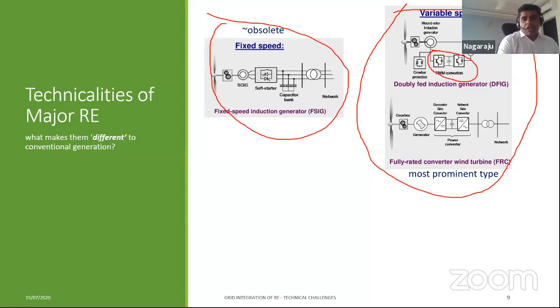Then we moved on to the full converter technology, where the full energy source is interfaced to the grid through this power electronic converter. So the converter is acting as a transmitter of the energy from the source to the grid. This is the grid, and this is the source. Even the doubly-fed machines are slowly fading away because they cannot be fully controlled. Through the rotor excitation, you can control only up to around 30% in terms of speed. So they are slowly going back in the stack, whereas the full converter wind turbines are now taking over the market. So they are now prominent.